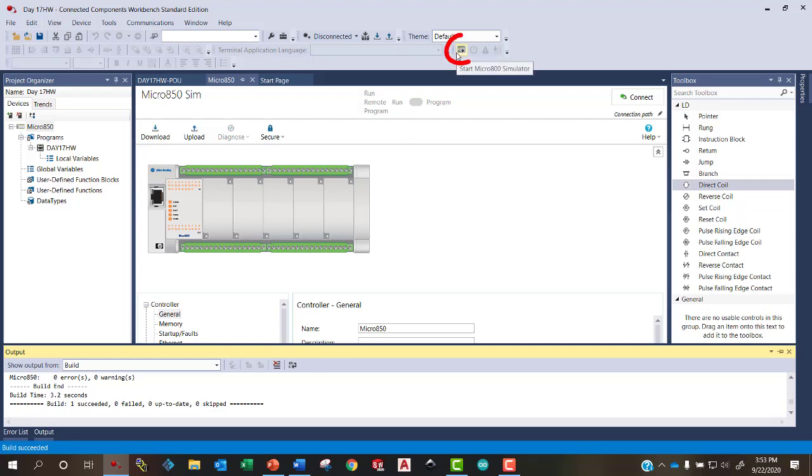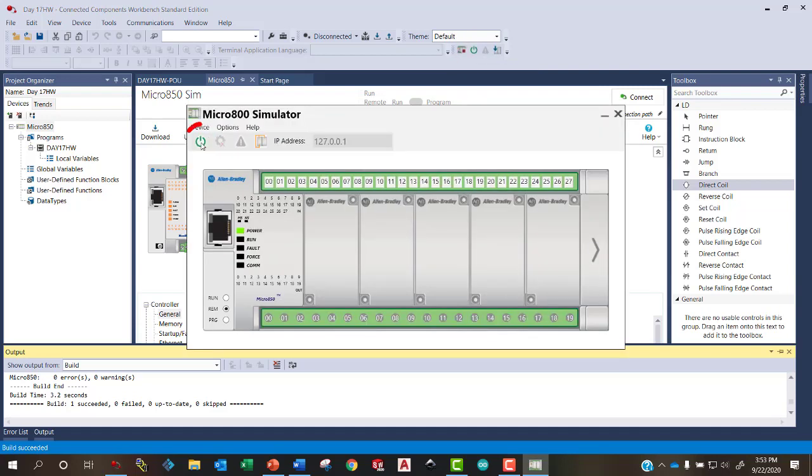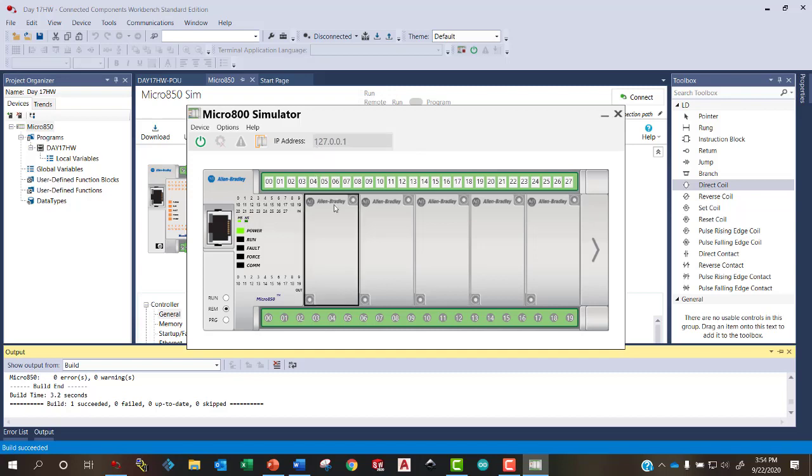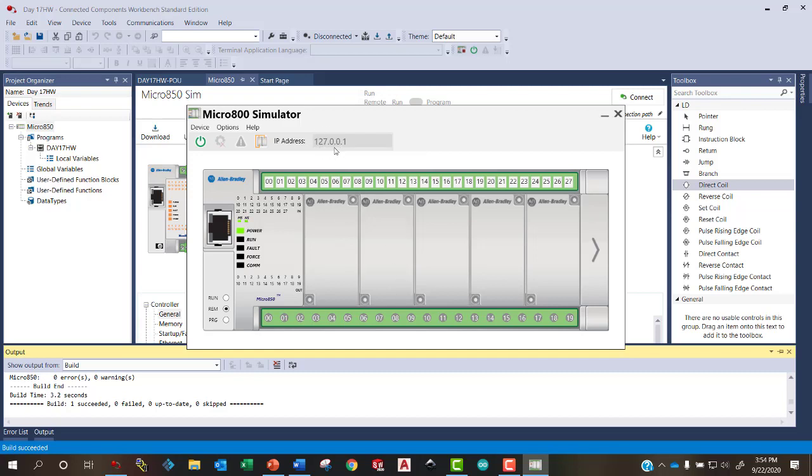Now we can go ahead and turn on the micro800 simulated PLC. Here's the power button. And we want to make sure the IP address is set to 127.0.0.1. This is the loop back IP address. So we actually don't have a PLC connected to our ethernet port. The PLC is internal to our computer. And so this IP address basically loops back to our own computer.